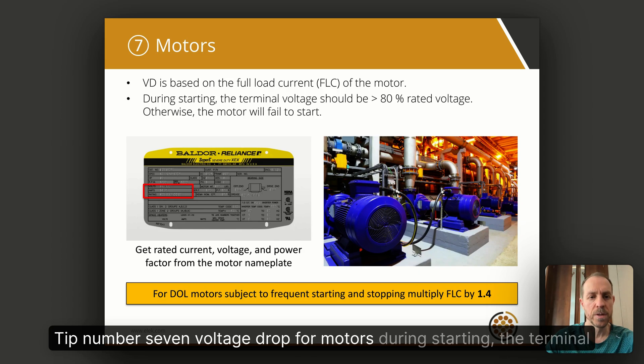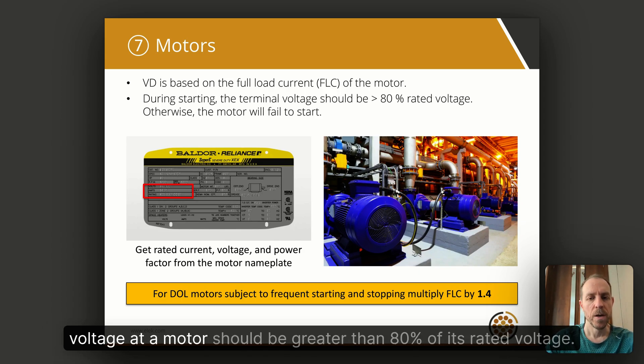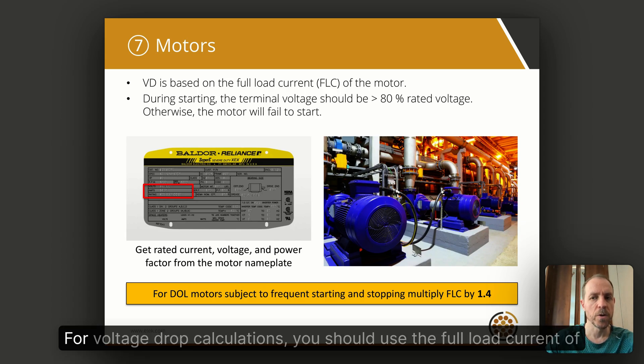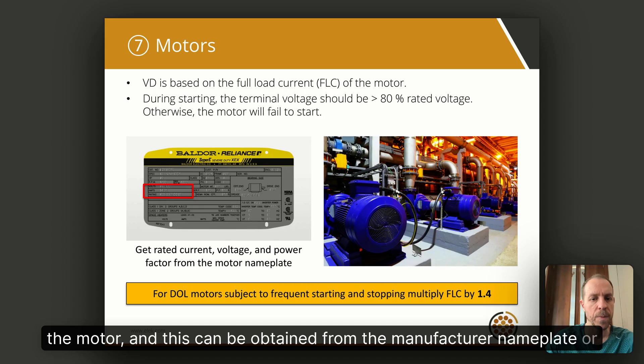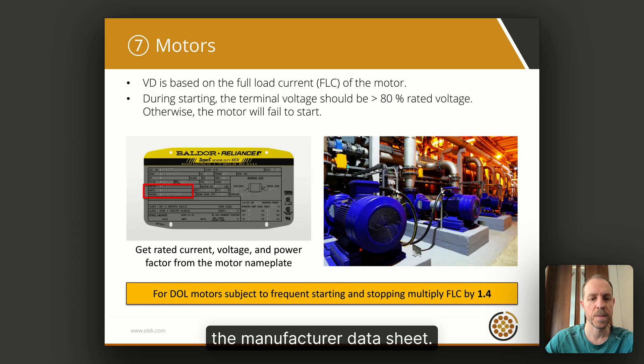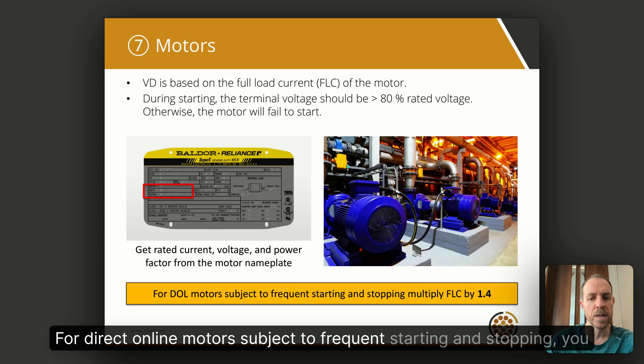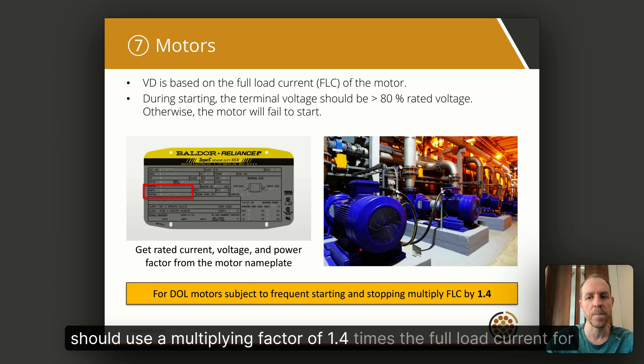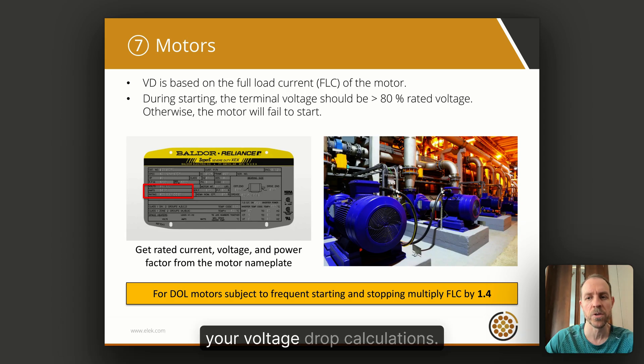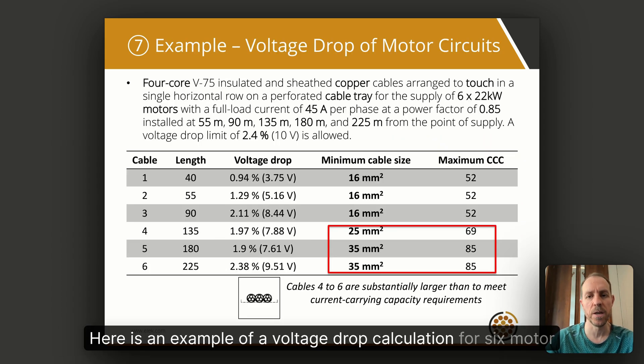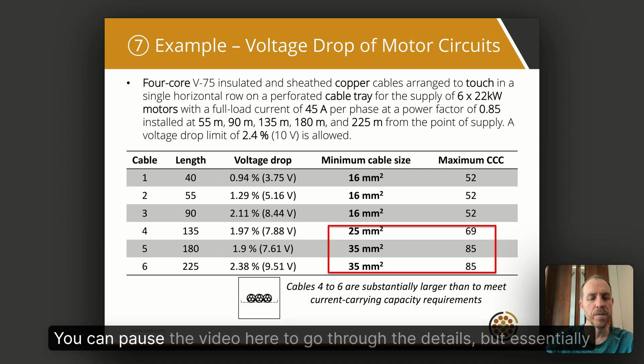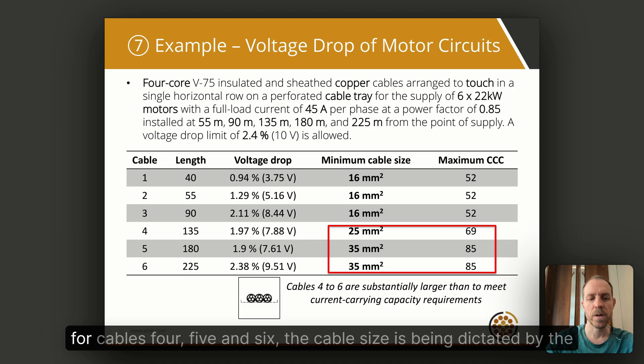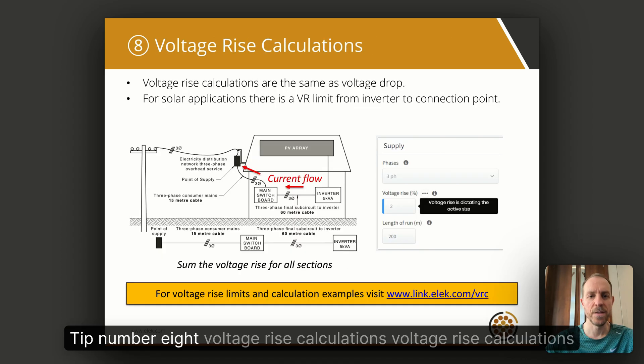Tip number seven: voltage drop for motors during starting. The terminal voltage at a motor should be greater than 80 percent of its rated voltage, otherwise the motor will fail to start. For voltage drop calculations, you should use the full load current of the motor, which can be obtained from the manufacturer nameplate or data sheet. For direct online motors subject to frequent starting and stopping, you should use a multiplying factor of 1.4 times the full load current. Here is an example of a voltage drop calculation for six motor circuits — for cables 4, 5, and 6, the cable size is being dictated by the voltage drop.